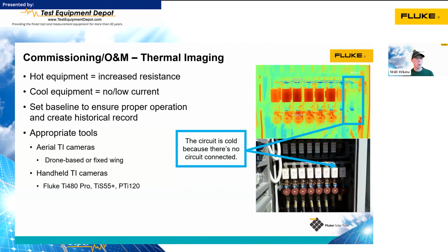The nice thing about the higher resolution is that you can get further away from the electrical equipment and still get good high quality photos. So you can be outside the electrical hazard zone with the system operating and still be able to get good thermal imagery. The TI 480 also has swappable lenses. So it comes with the standard lens. You can also add a telephoto and a wide angle lens as well.